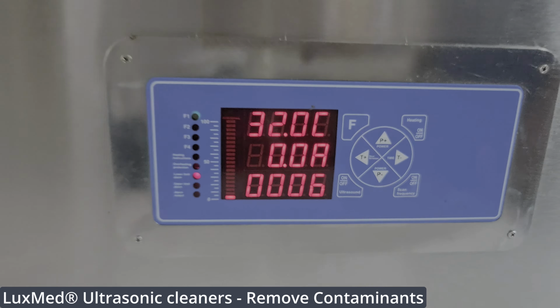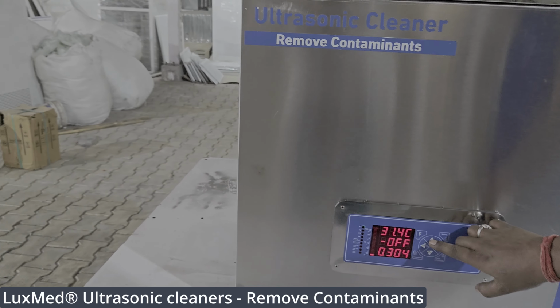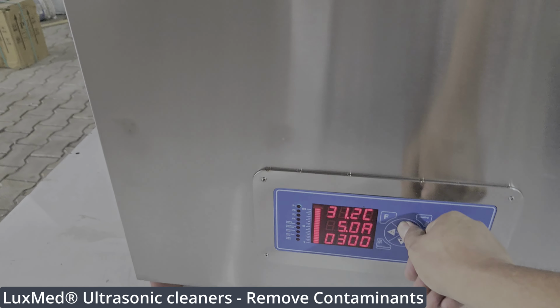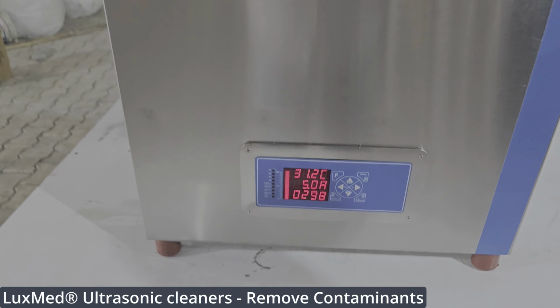1. Sound wave generation. An ultrasonic generator produces high-frequency electrical energy, typically in the range of 25 to 50 kHz. This energy is converted into mechanical vibrations by an ultrasonic transducer. 2. Cavitation. The transducer generates high-frequency sound waves, which are transmitted to the cleaning liquid. As the sound waves pass through the liquid, they create pressure fluctuations, periods of compression and rarefaction. During rarefaction, low pressure, small bubbles, cavitation bubbles, are formed. Bubble collapse and shock waves.